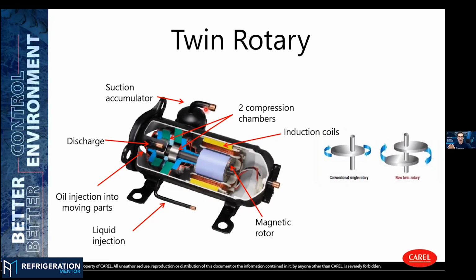And I like that you brought up the envelope, because we're going to get into that in a little bit. But this is so key when you're working with these compressors, especially if you're a designer out there, or a technician, to understand where the compressor should be running. Because when you run outside those operation limits, that's when you run into issues.